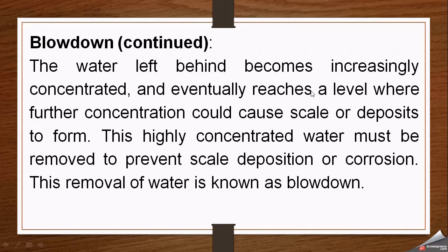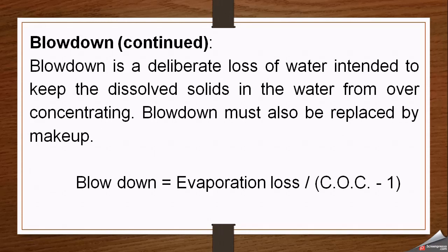The recirculating water becomes increasingly concentrated as dissolved solids increase while water quantity decreases. Eventually a point comes when further increase in concentration could cause scale or deposits to form in the system. This highly concentrated water must be removed to prevent scale deposition or corrosion. The removal of this concentrated water is known as blowdown — a deliberate loss of water intended to keep dissolved solids from becoming over-concentrated. Blowdown can be calculated as: blowdown = evaporation losses divided by (cycles of concentration minus one).